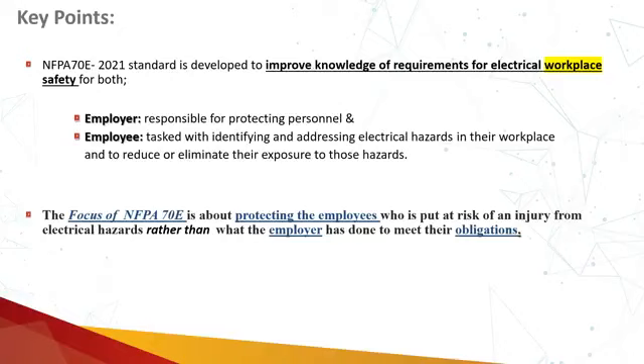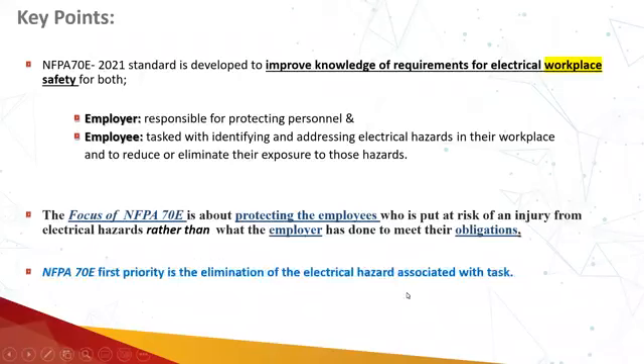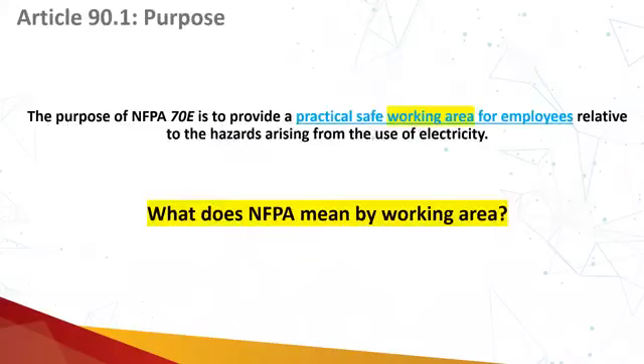OSHA requires that you protect your employees, but whether by following the 70E requirements or any other requirements is up to the employer. Okay, so 70E is basically adopted by employers in order to protect employees under their control, who are put at risk from an injury from the electrical hazard, rather than what the employer has done to meet their obligations. And NFPA 70E's first priority is the elimination of the electrical hazard associated with the task. Then we discussed that the purpose of NFPA 70E is to provide a practical safe working area for employees related to the hazard arising due to the use of electricity.